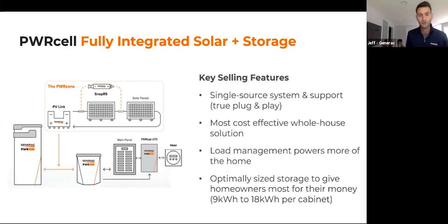All devices connect on a 380-volt DC bus — a series of conductors that transmit power and data. Our PV links communicate to our inverter over the power line; the battery communicates to the inverter over the power line. All devices communicate together to decide how much power is flowing and how much is going to the home at any given point. Generac even manufactures the transfer switches — we ship over 600,000 transfer switches a year, so launching the PWRcell ATS was no big feat for us. Load management is also all by Generac, a product we've been shipping for five or six years.